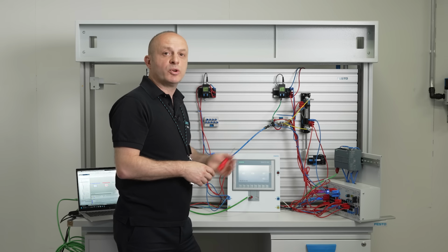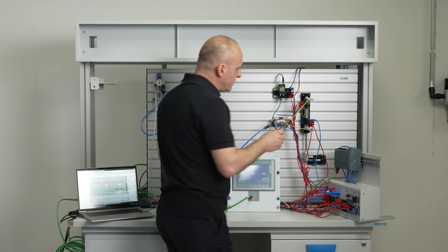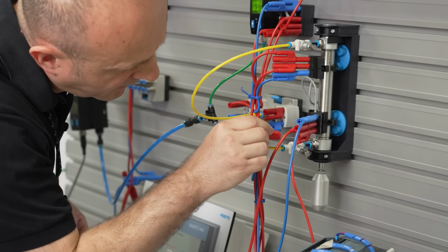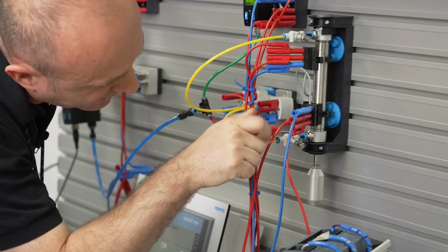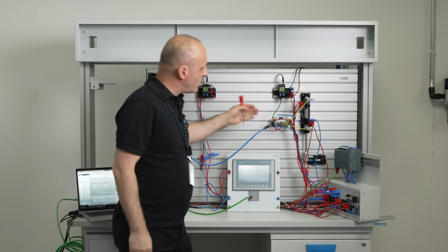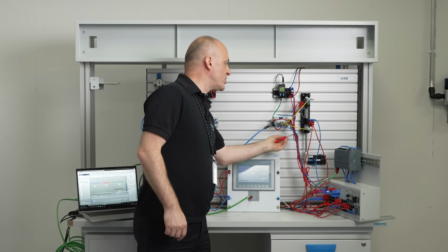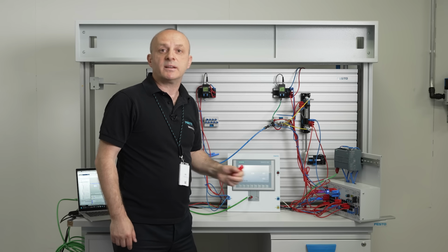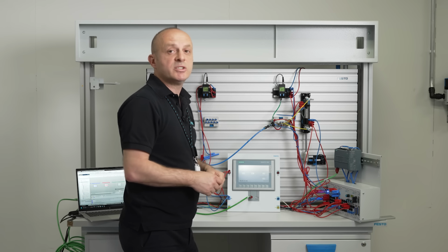At the moment, the machine is working all right, it's advancing and retracting. But what I will do is come here and turn the cushioning adjustment all the way in, okay? And the machine stops, because the cylinder cannot advance fully; some air is trapped here. I haven't noticed anything. I moved on, and another maintenance engineer comes here and says the machine is not working.